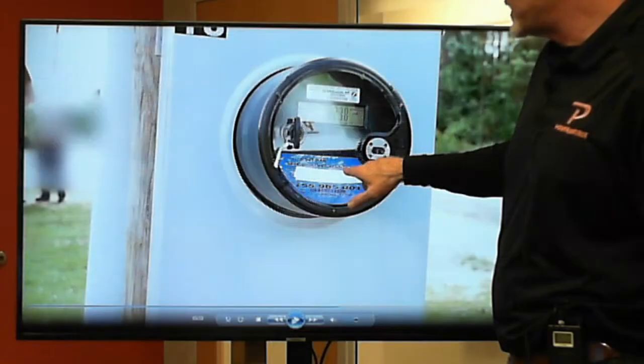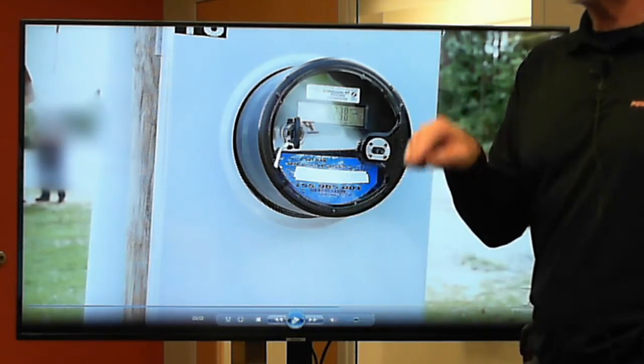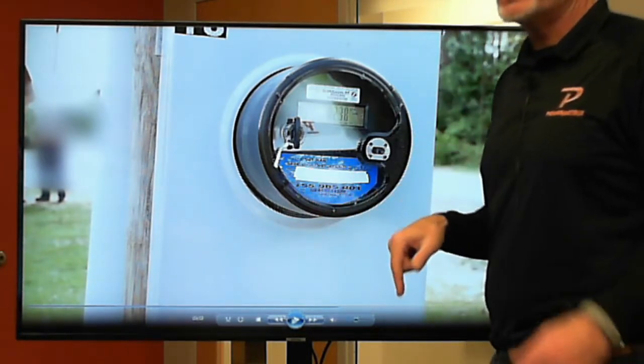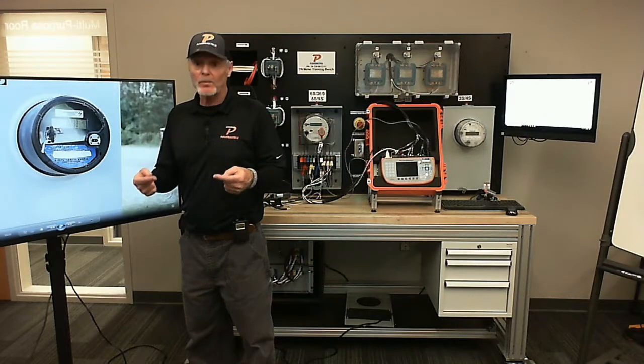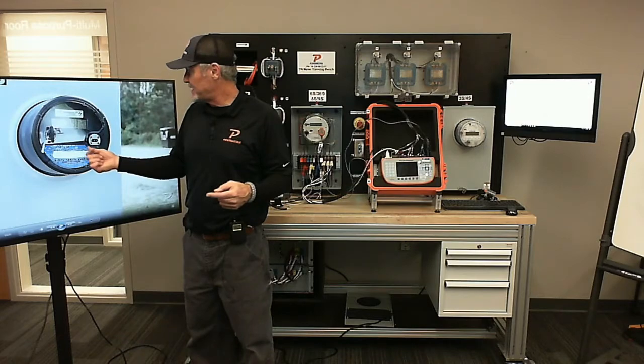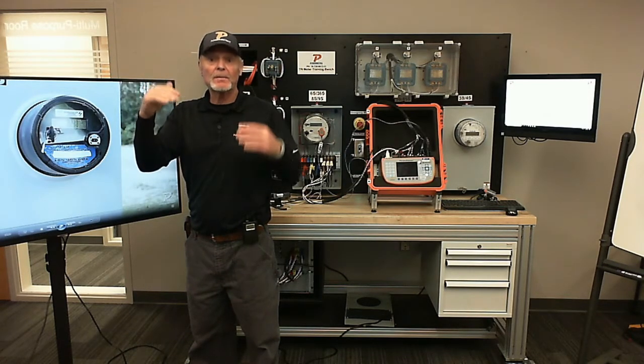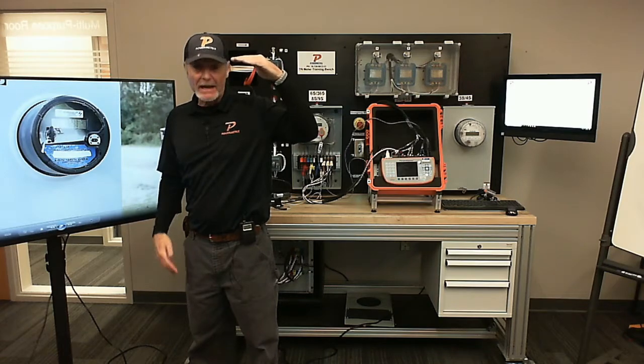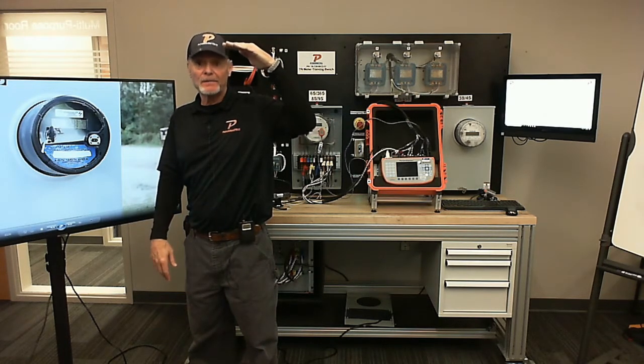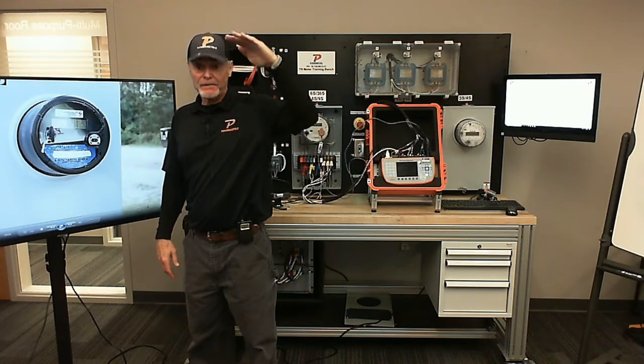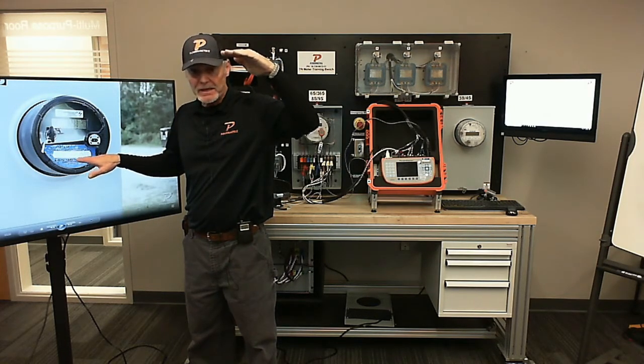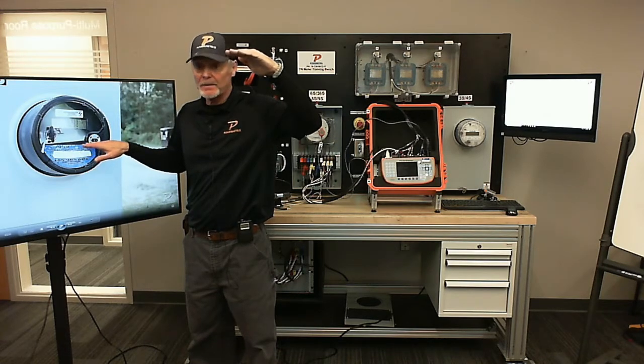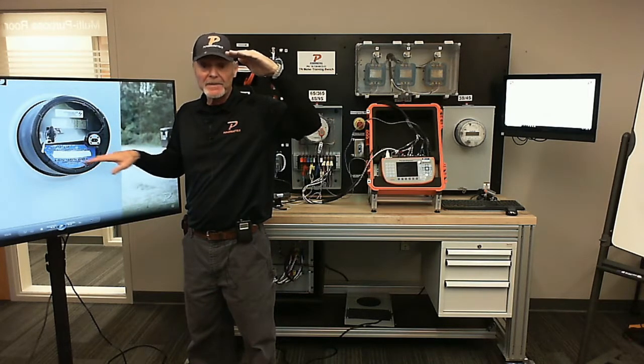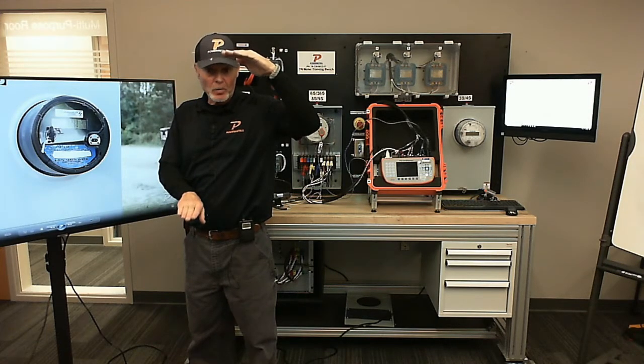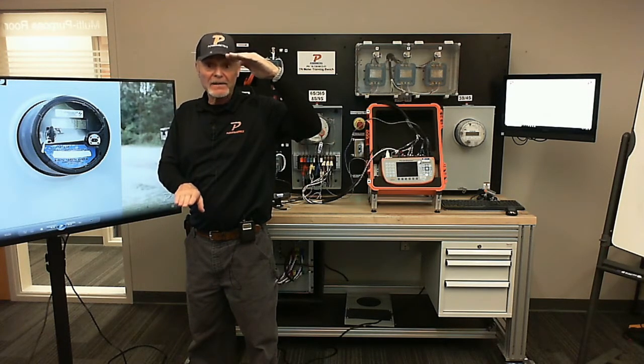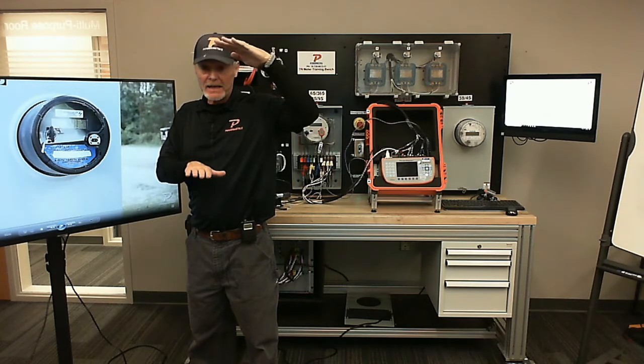Also, you'll see on there it has TA equals 2.5. That 2.5 is important to us because if you're doing a phantom load test at this site, where you're going to generate the load on there, that TA 2.5 is now your full load. So my full load is 2.5 amps, right? And remember, there are 3 tests: full load, power factor, light load. My full load is the 2.5 right there off the face of the meter. It tells you, so you always know what your full load is going to be from the face of the meter, the TA, 2.5. Then according to ANSI, my light load is always 1/10 of that, so it's going to be 0.25. Just slide that decimal to the left one, right? So that's divided by 10.